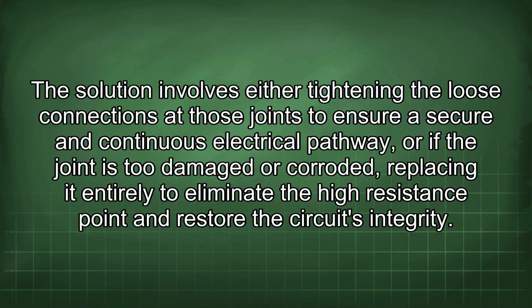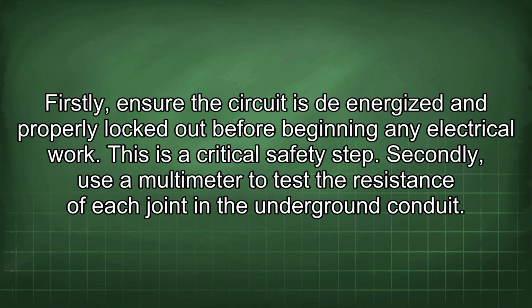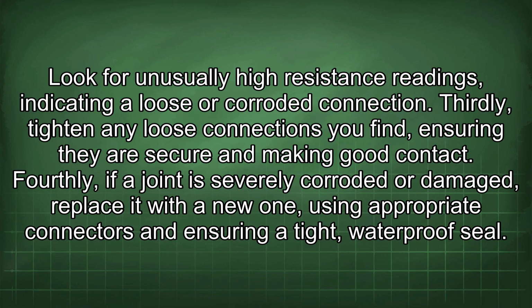Firstly, ensure the circuit is de-energized and properly locked out before beginning any electrical work. This is a critical safety step. Secondly, use a multimeter to test the resistance of each joint in the underground conduit. Look for unusually high resistance readings indicating a loose or corroded connection. Thirdly, tighten any loose connections you find, ensuring they are secure and making good contact.